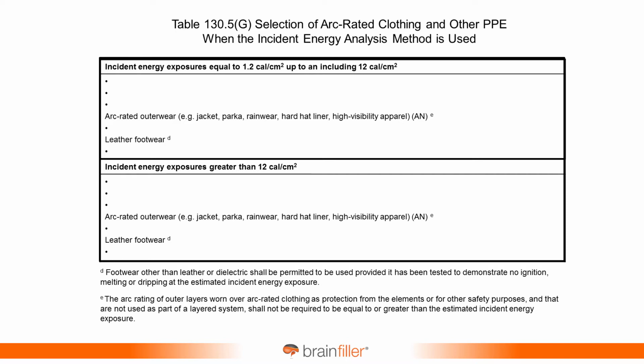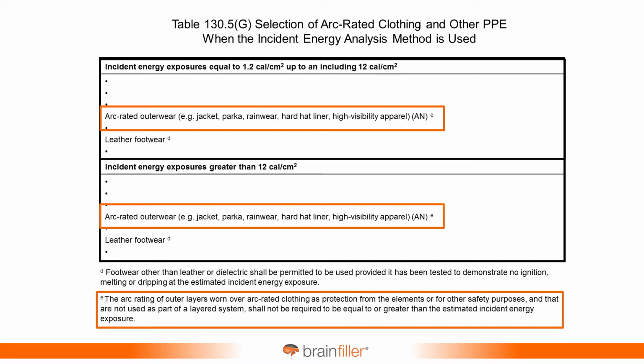And so now for the arc-rated outerwear or high visibility apparel, they used to have the word safety in there, that was removed. Down at the bottom, that's where you're going to find the note about the arc rating of the outer layer worn over the arc-rated clothing as protection from the elements or for other safety purposes and that are not used as part of a layered system shall not be required to be equal to or greater than the estimated incident energy exposure. That would have just been difficult.